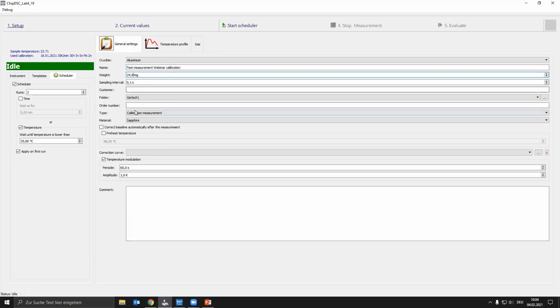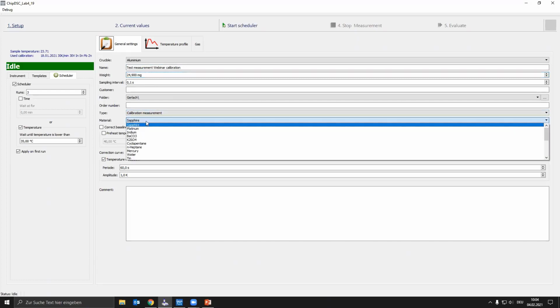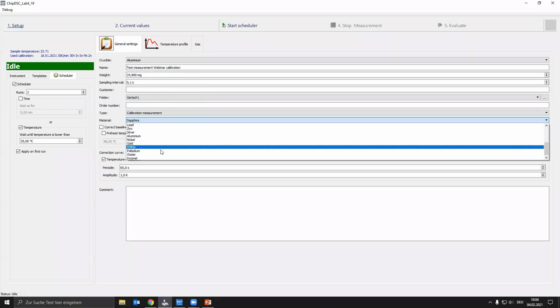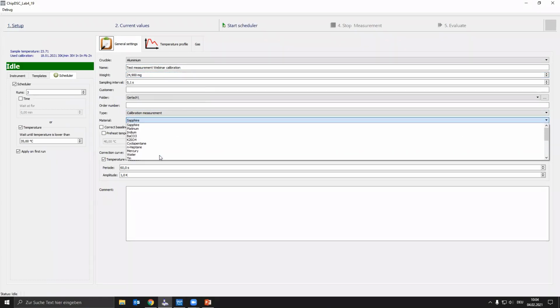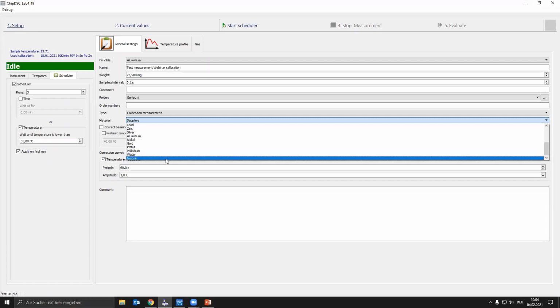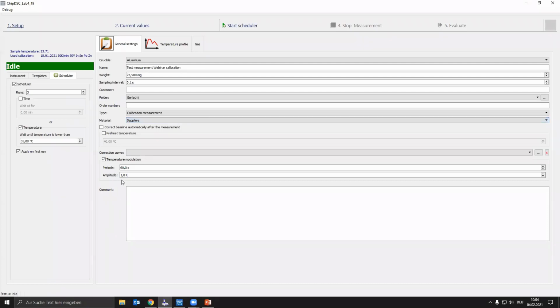And you just have to change the type of your measurement. And of course, you have to select the material you're using. And what you can see here is there are already some materials inside you can use for the calibration of your temperature modulation. What else is important? You have to leave all other settings like the temperature modulation and the temperature profile the same.